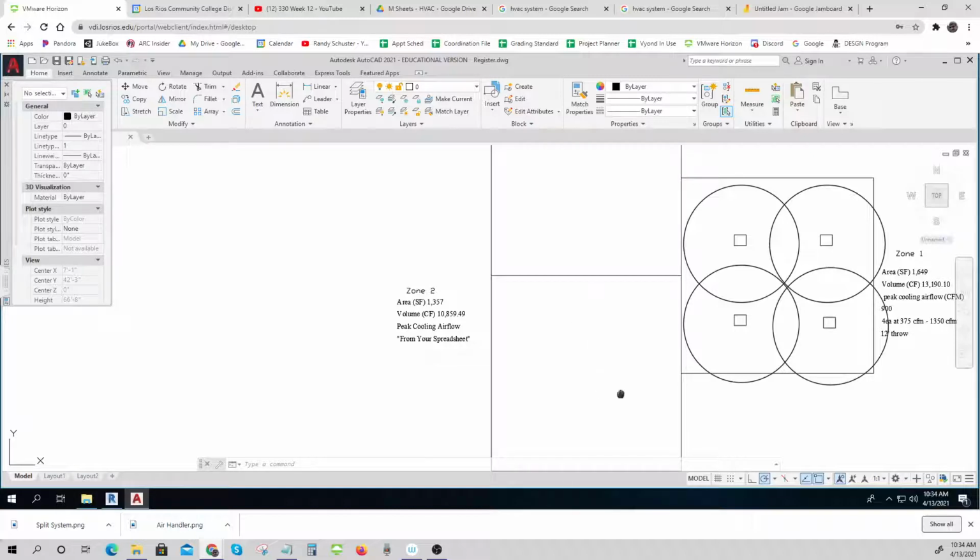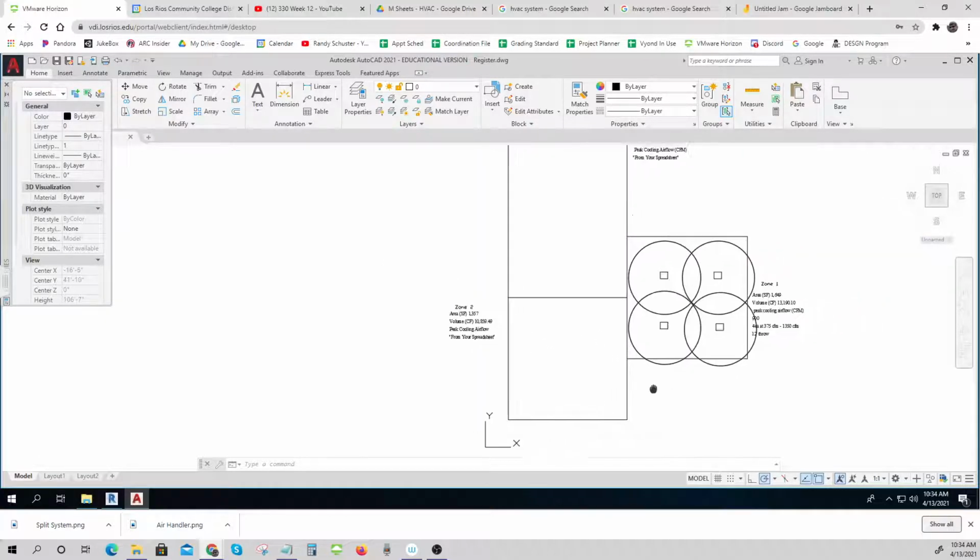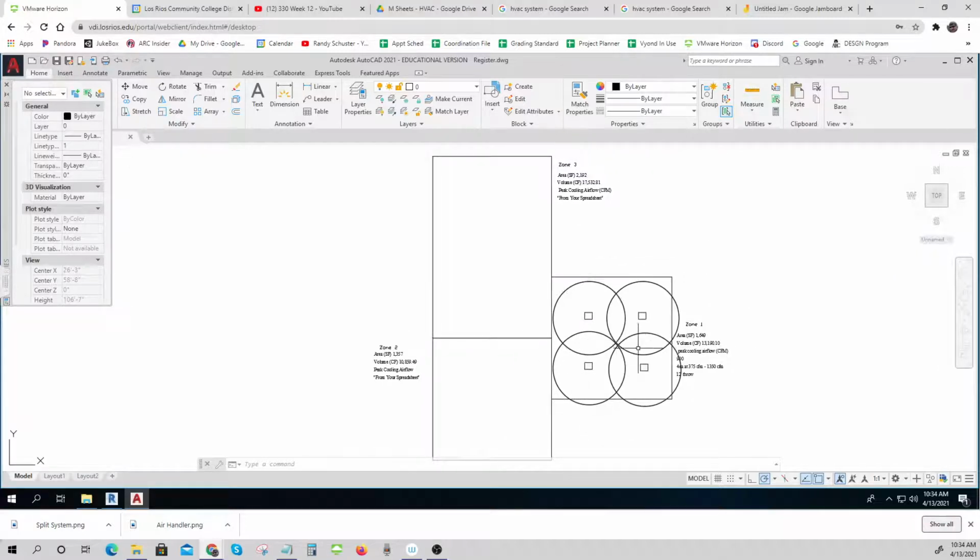But you've got a couple that are getting up into the 250 range that you'll need an 8x8 neck. So again, this is actually easier because it's just like 1, 1, 1, 1, 1, 1, 1, 1, 1. There. And just pick the correct neck size. Much easier than trying to figure this out.